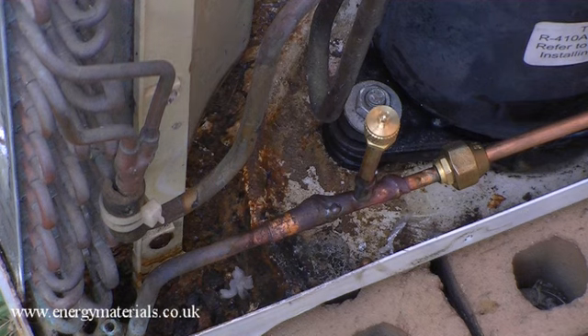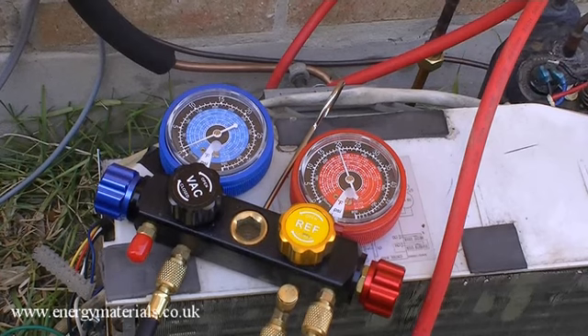One little trick is after you've applied the soap solution, which can be dish soap, make sure you wash it down with water afterwards to prevent any corrosion, as dish soap can be quite corrosive. So after applying the dish soap, we didn't see any bubbles in any of our fittings. We've had the system under pressure, all the valves have been isolated, and we've maintained that pressure for 6 hours. All the joints have been checked with bubble solution, and no bubbles have been detected, so that's encouraging. So we haven't got any gross leaks.